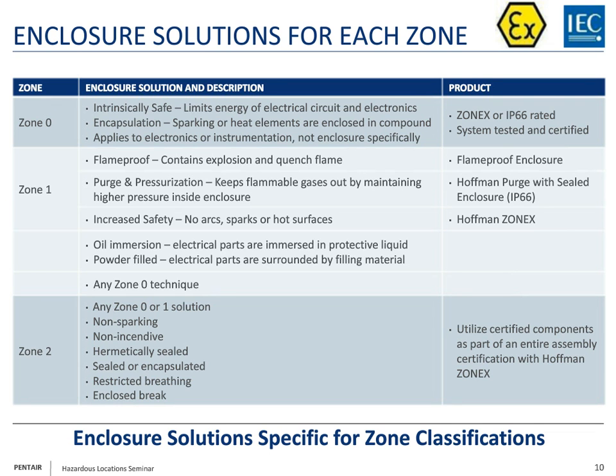In Zone 2, you can use any Zone 1 solution, but you have some other components or other tricks in your bag, if you will. You can use non-sparking, non-incendive, hermetically sealed components, and you can use those components as a completely certified assembly with an increased safety certified enclosure. That is what we typically see in those environments.